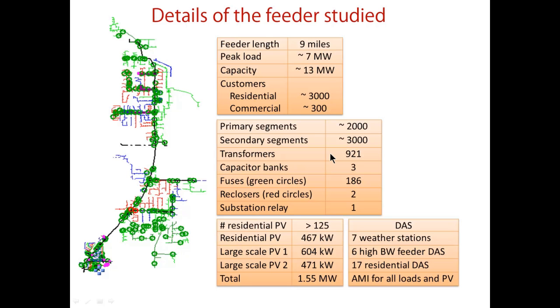There are close to 1,000 transformers, 3 capacitor banks for voltage control, and there are about 186 lateral fuses, in addition to all the fuses on the primary of the transformers. There are also 2 reclosers. The reclosers are shown by these red circles. There's one mainline recloser, another recloser for this main lateral. And of course, the substation has this relay.